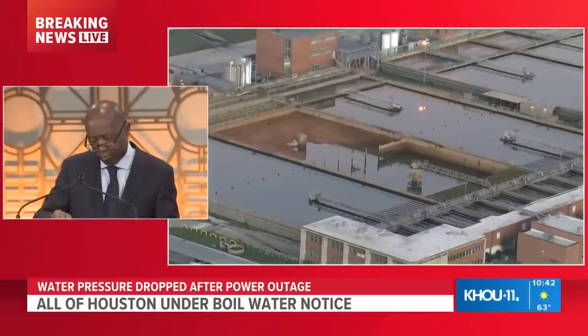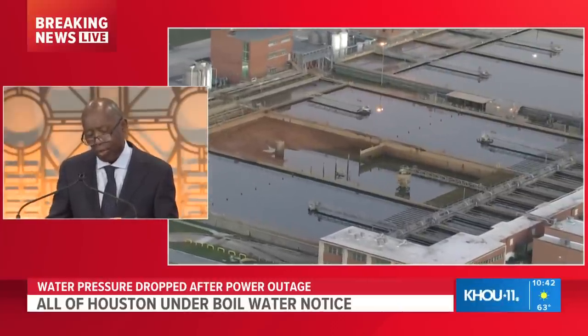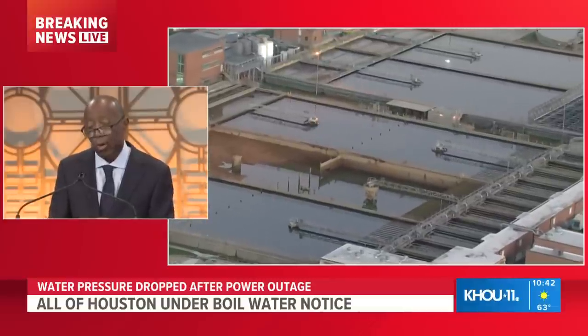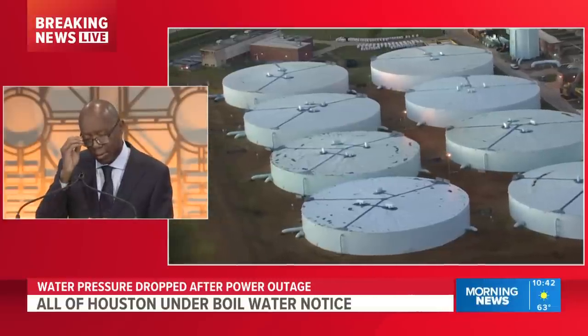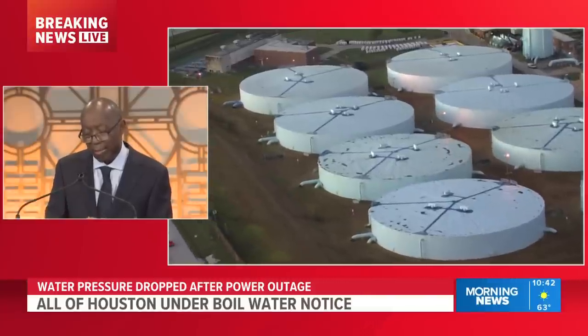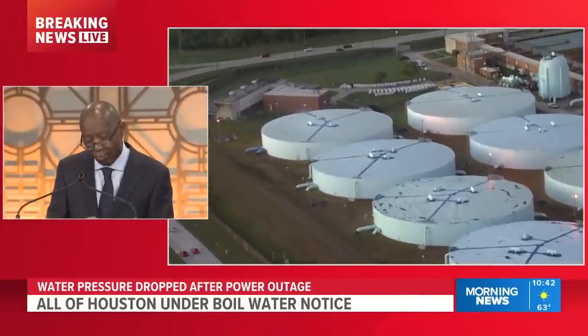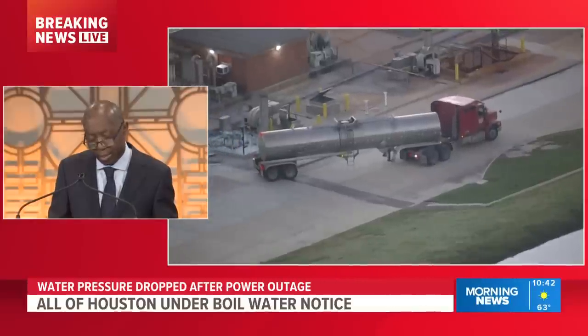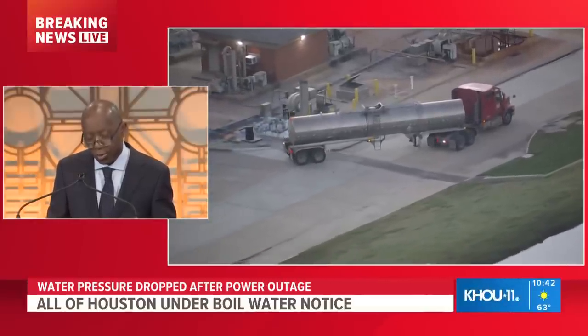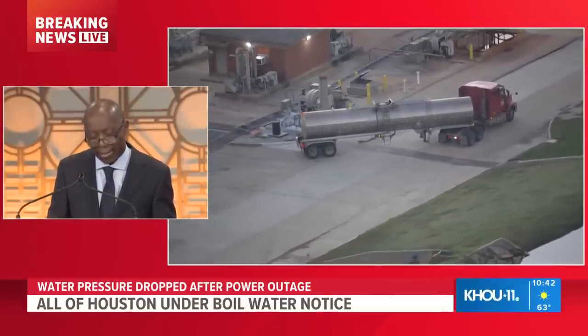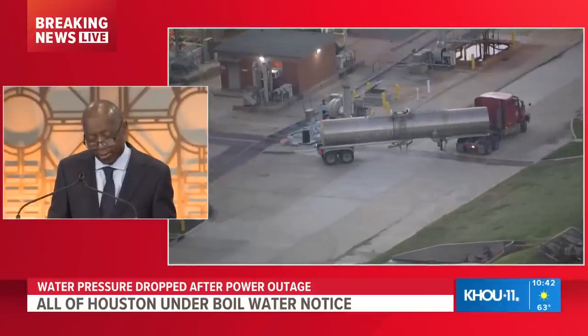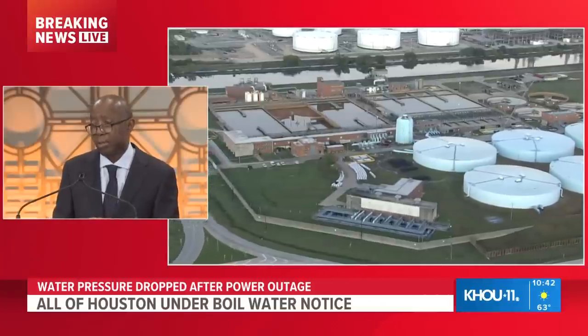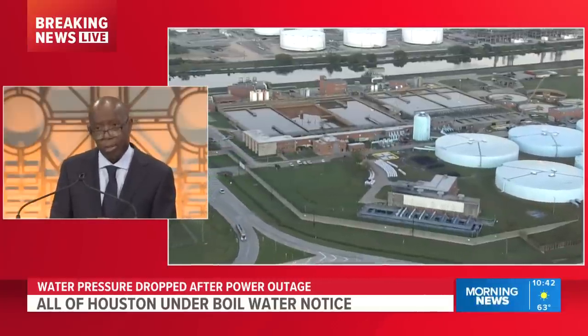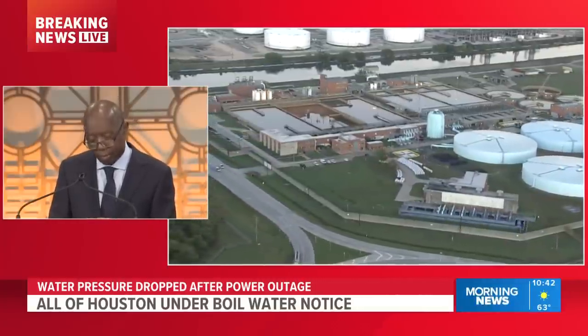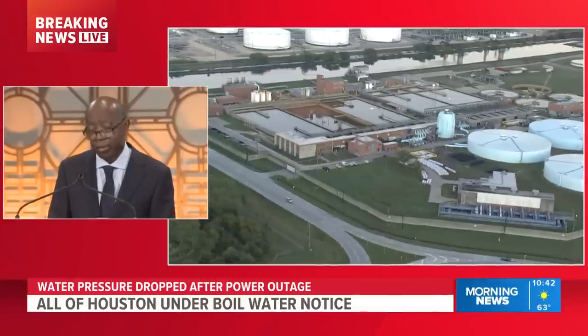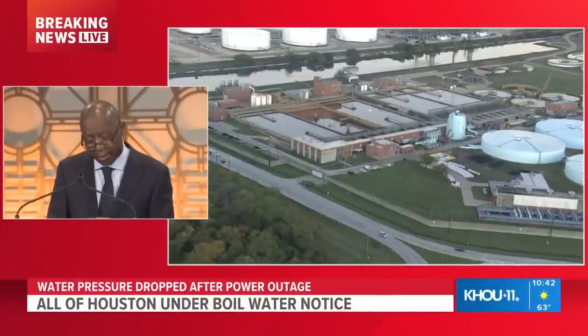Power was restored at 12:30 p.m., and full water pressure was restored to all three plants by 3:30 p.m., with all locations back at 35 psi. Further investigation and testing on the breakers, transformers, motors, and feeders found a bad cell in the Plant 1 transformer. I've asked for a complete diagnostic review of this system to verify and identify how we make sure it does not happen again.